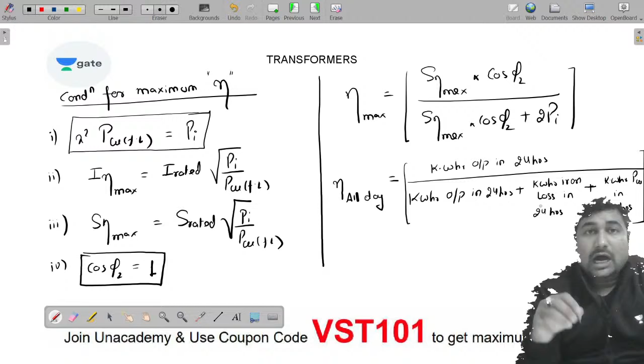Now one thing to remember about all day efficiency is the iron loss. If the transformer is on no load, no load losses still occur. Output is 0, core loss and copper loss calculation give 0 output, but the no load loss is still present when the transformer is on no load.